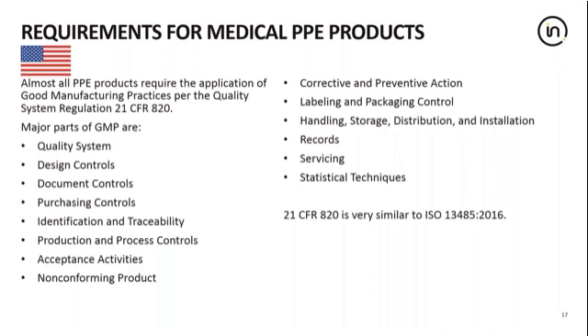The key points to highlight on this slide are the quality system, because there should be controls in the production process to ensure that production is monitored and the product is consistent and compliant. The design control, because the design should be documented, and this may include design drawings and may include details of the filtration medium, for example, and design verification, and could include details of the testing program, such as ASTM F2100 for medical masks.